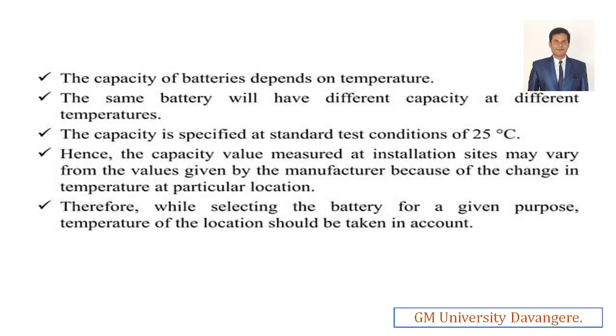Next, the capacity of the batteries depends on the temperature. As I discussed during the state of charge of the batteries, when the battery starts charging and discharging, right? During that instant, the battery temperature may rise and lead to degradation of the battery life, and the C rate also. The capacity of the batteries is a very important factor if you consider the temperature, right?